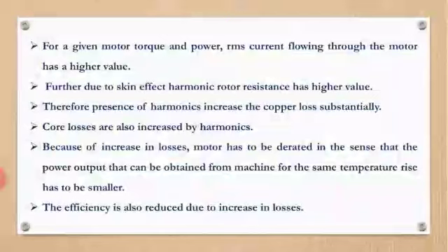It means the rating of the motor, for example 10 kilowatt, will go lower, say 6 to 7 kilowatt, for the same temperature rise as that of the 10 kilowatt rating. So it will be derated. The efficiency is also reduced due to the increase in losses. These are all the effects of the harmonics.